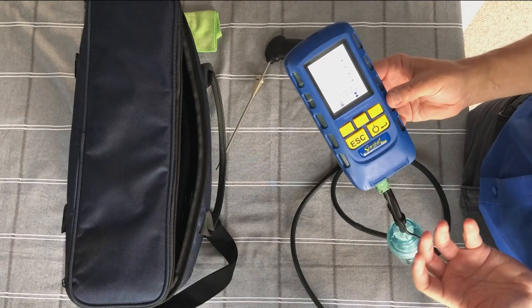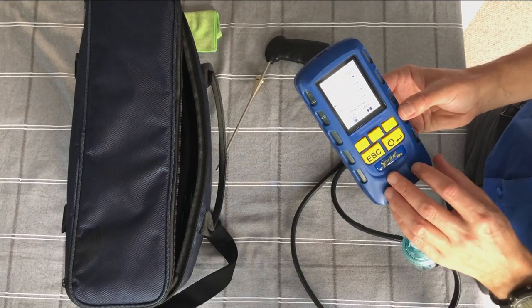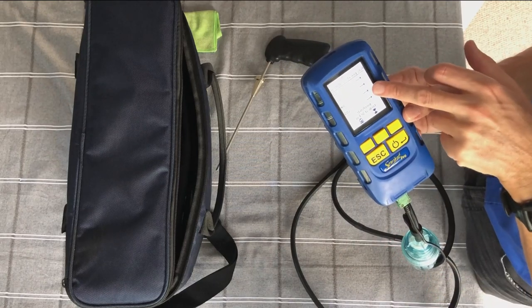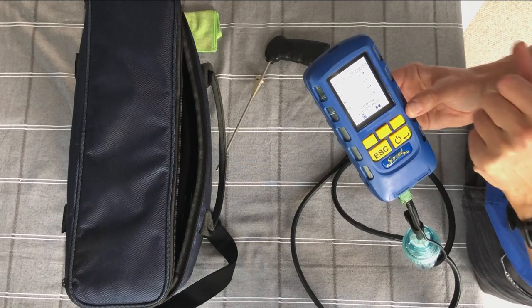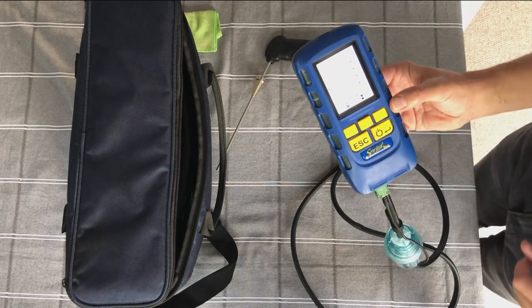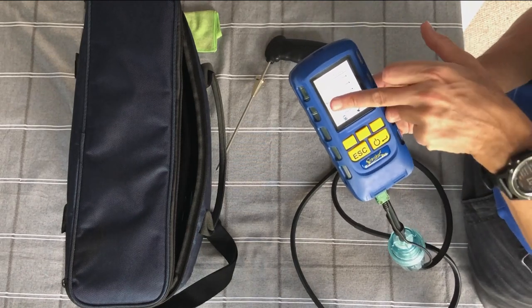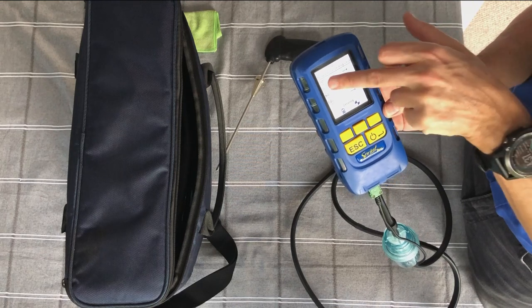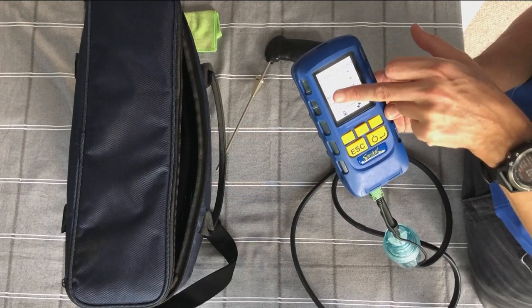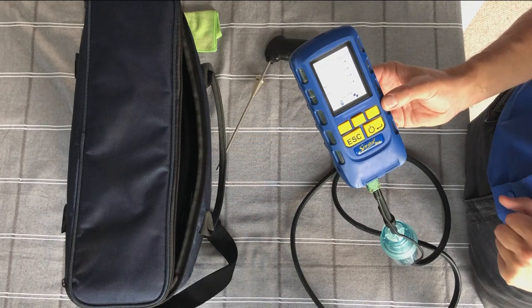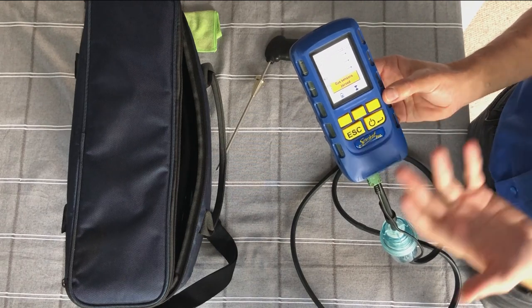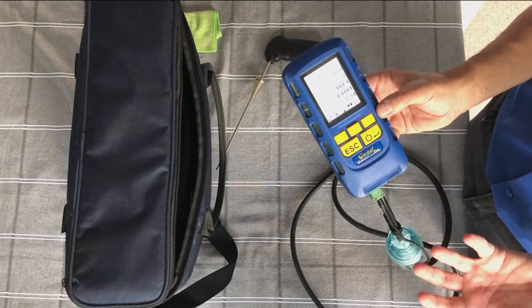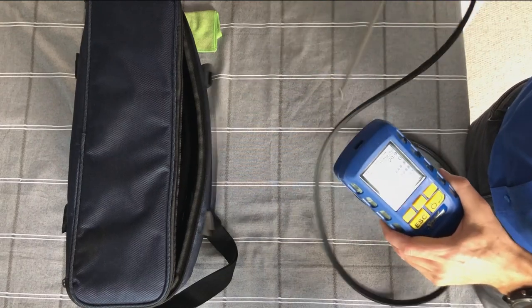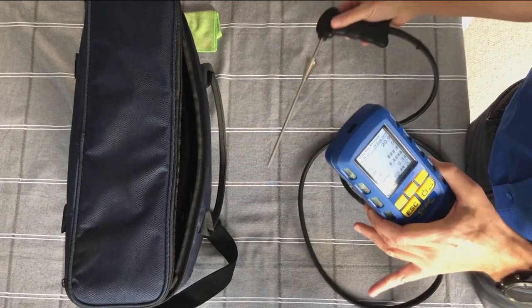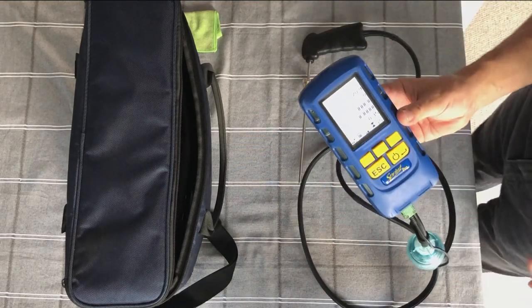And now we start going through the zero process. As I said earlier, this is a Pro 6, so it's a fully populated one with NO and CO2 sensors. So it takes slightly longer, but if you've got a Pro 3 or Pro 1 or Pro 2 or something like that, you'll only have the CO and the oxygen that'll be zeroing. So that's now zeroed, and now I'm in flue gas mode. I'm ready to go and start taking readings. It really is that straightforward.